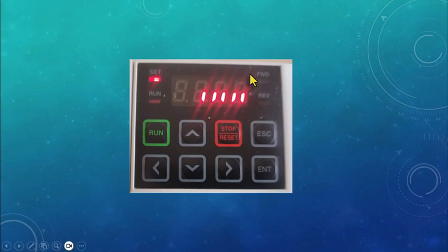For example, here, this bit, P2, P3, P4, and P5 from right to left correspond to digital inputs P1 to P5, respectively. Now, since the bits related to all the digital inputs are low or off, all our digital inputs are in the normally open state, and it's the same for the status of the digital inputs. If the bit related to that digital input is low or off, that digital input is at logical 0, meaning it's inactive. And if this bit is high or on, that digital input is at logical 1, or it's on.